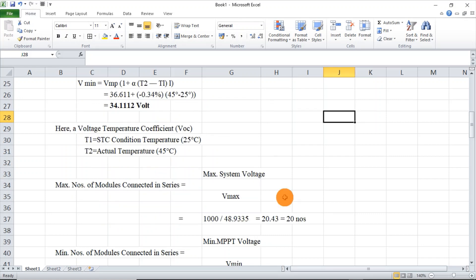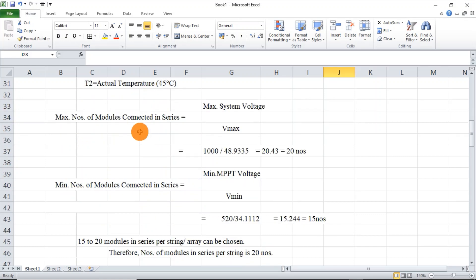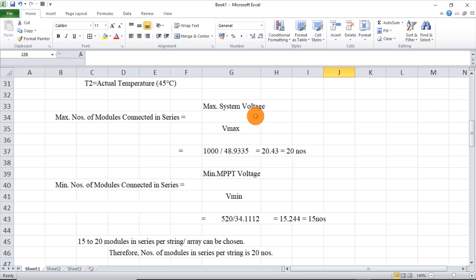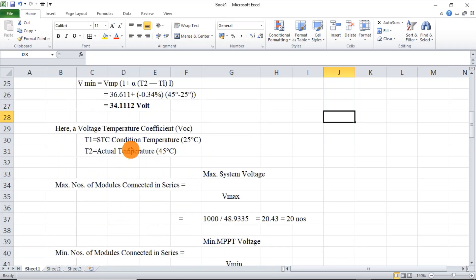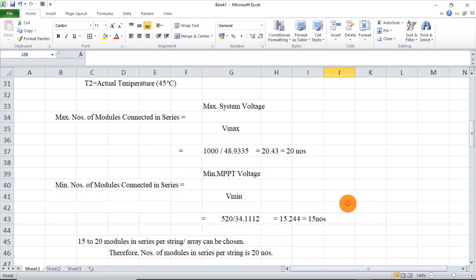Going for the maximum number of modules to be connected in series, we have the formula: maximum system voltage divided by Vmax. The maximum system voltage is the maximum MPPT voltage, which is 1000V, and Vmax we calculated as 48.9V. Equating this, we get 20.43, so that is 20. We can connect a maximum of 20 modules in series with this inverter.